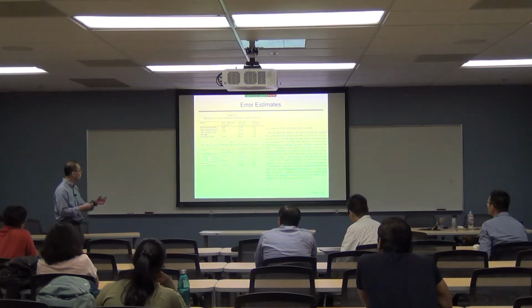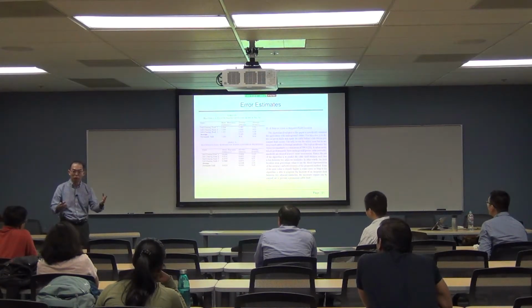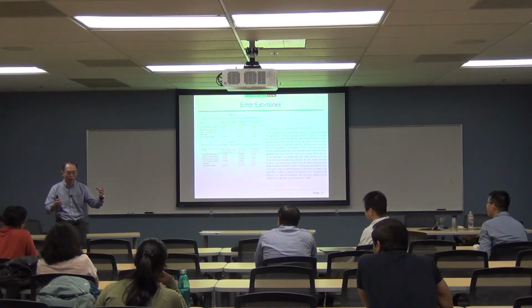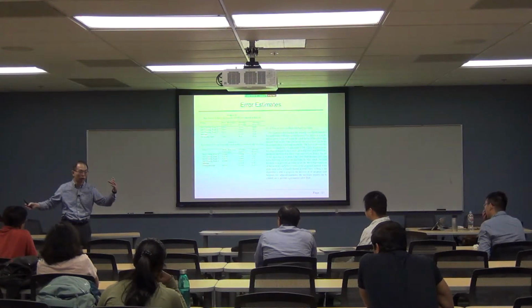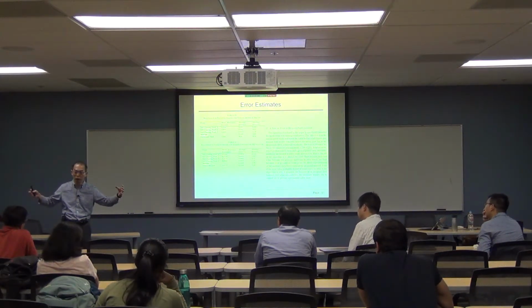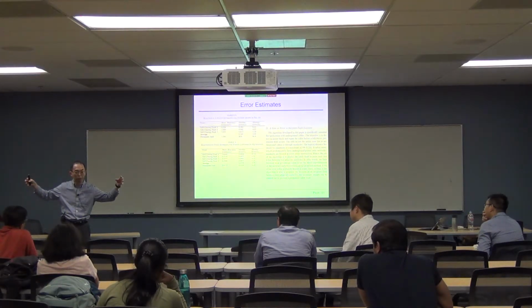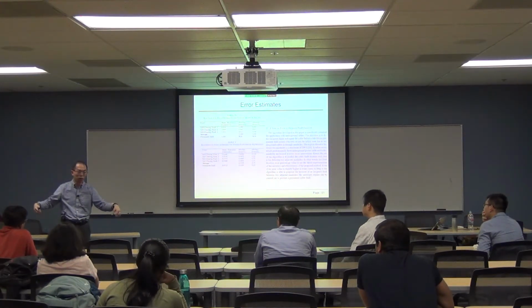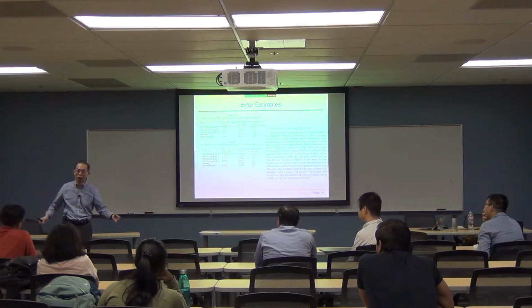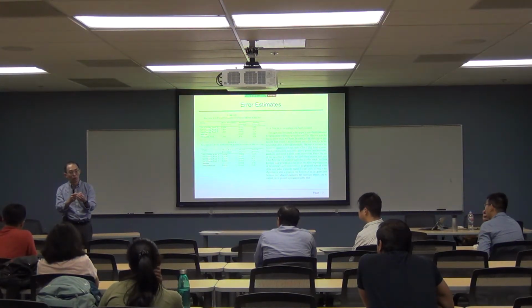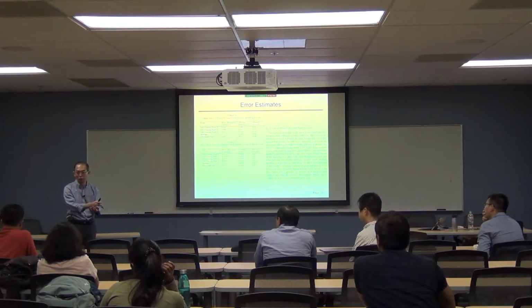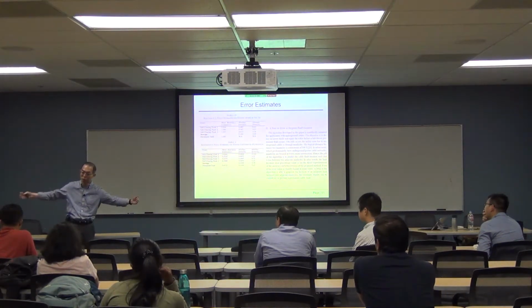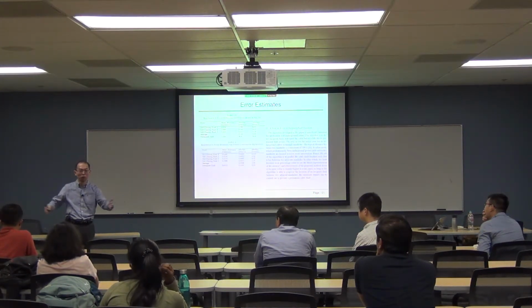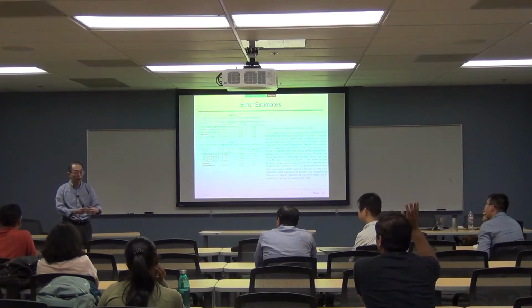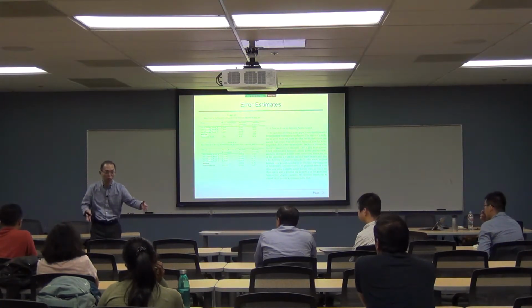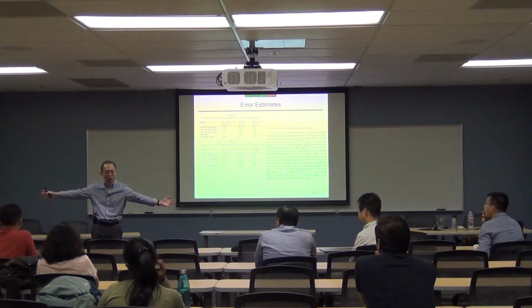When we are talking about cable faults, what we really want is the distance between two manholes, because as long as your estimates are accurate within one or two manholes, that is where the line crew goes into the manhole and fixes that portion. You don't have to get accuracy down to 10 feet or so. As long as it's within one manhole to another, typically 500 feet, that is good enough for them, because when they replace it, they don't replace just a 1 foot long cable, they replace some span of it.